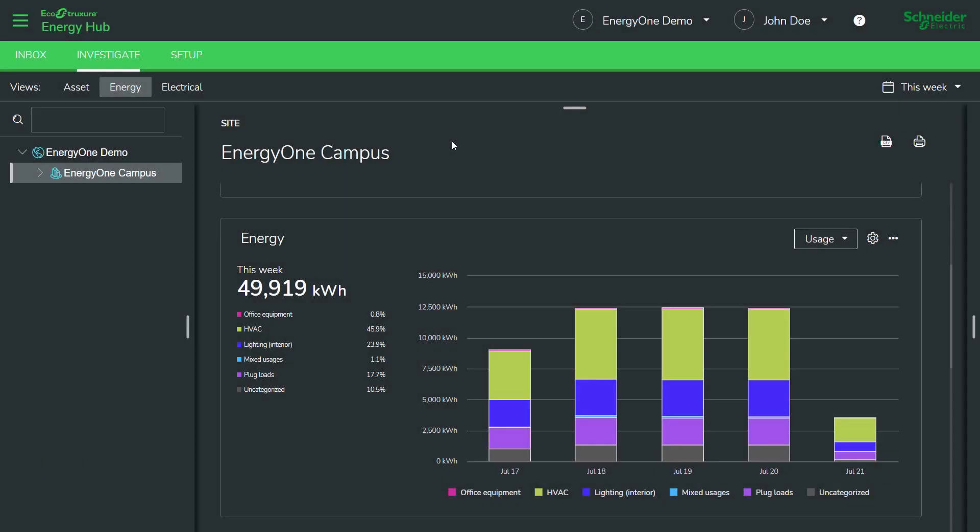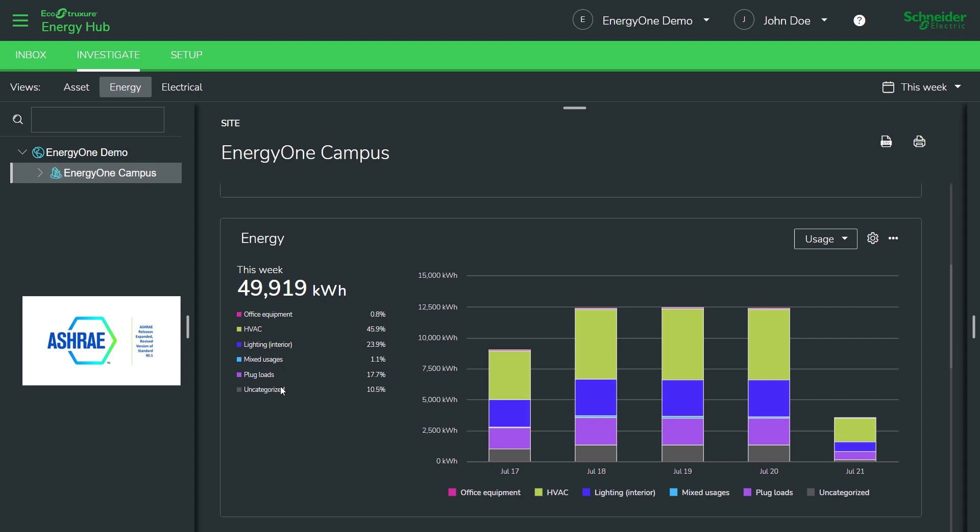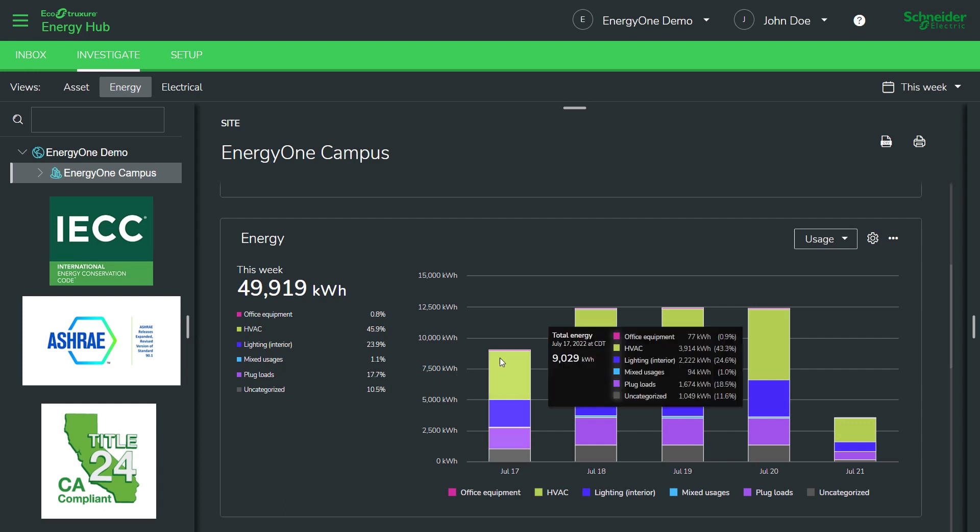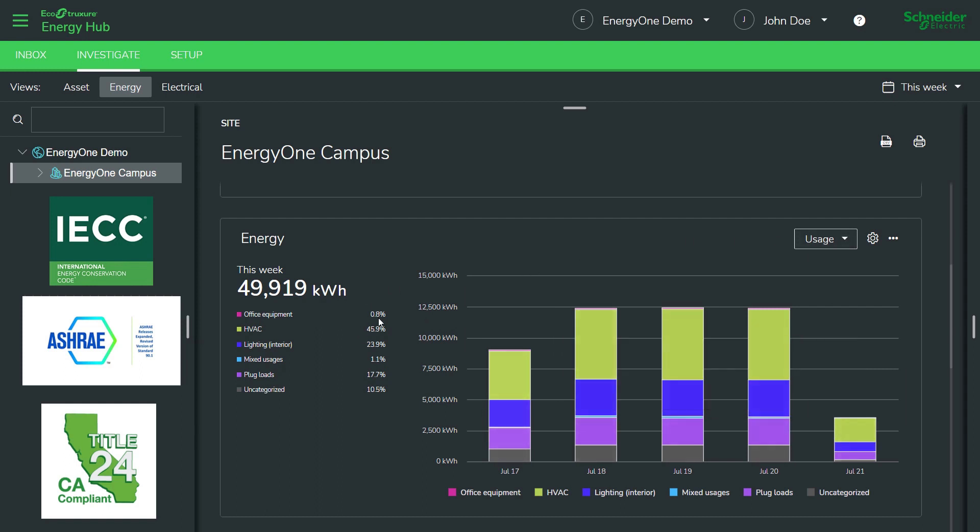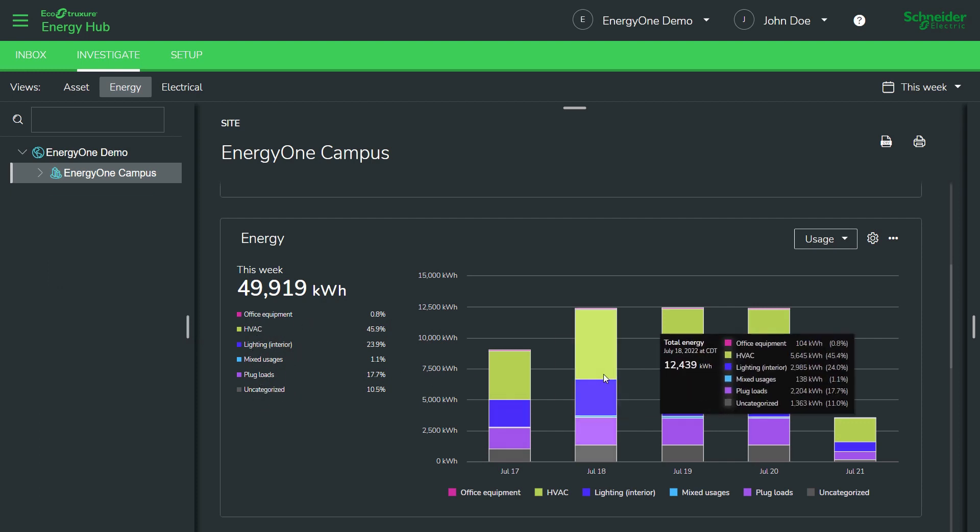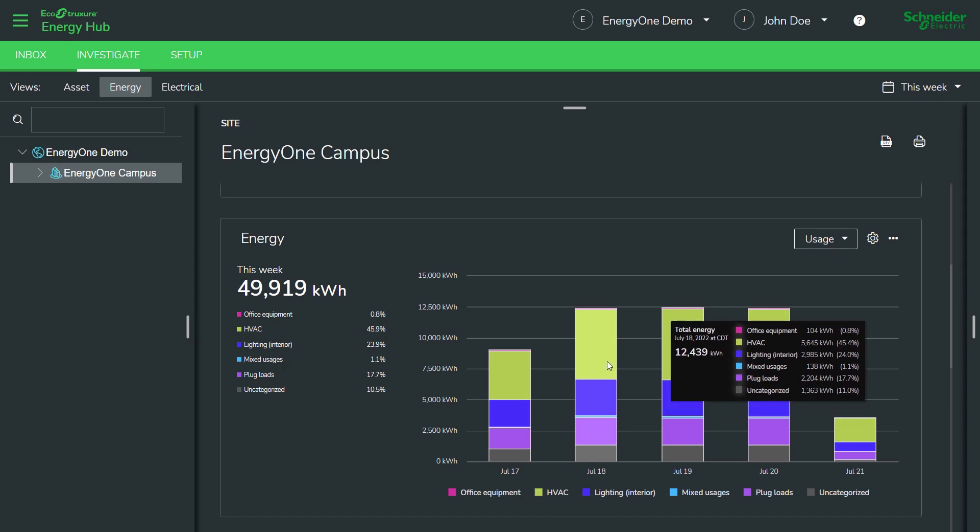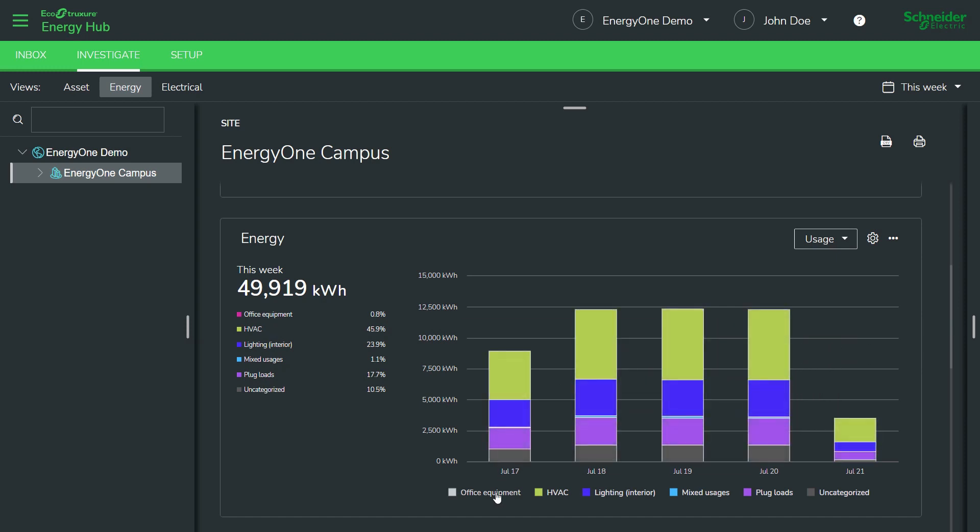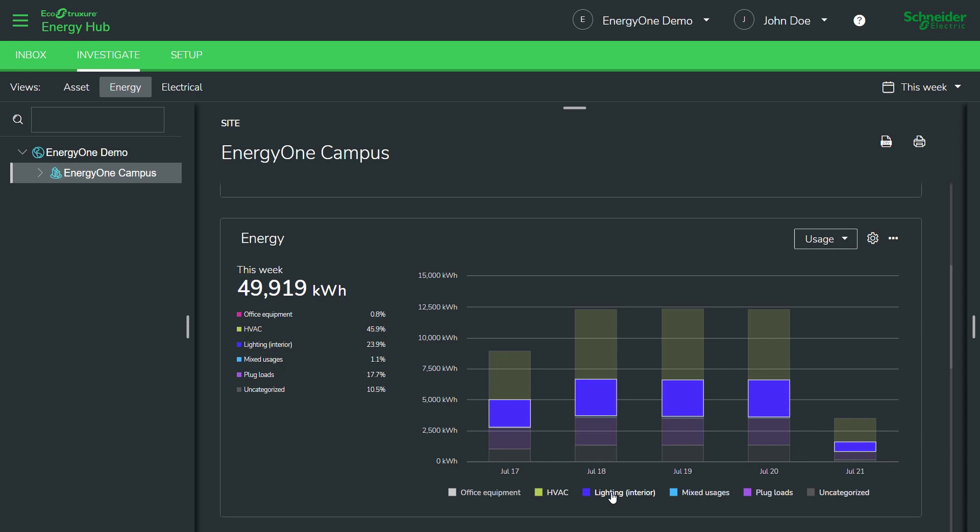Another really important view is the energy by load type and the reason this is important is that many electrical codes and energy codes require this data to be stored, collected, aggregated and reported on. For example, ASHRAE 90.1 and California Title 24 are two important national standards which require this data to be collected. As you can see, this view enables you to categorize energy usage by different typical categories like plug loads, lighting, HVAC, etc. You can also dive into particular categories that you're interested in and try and identify any anomalies.